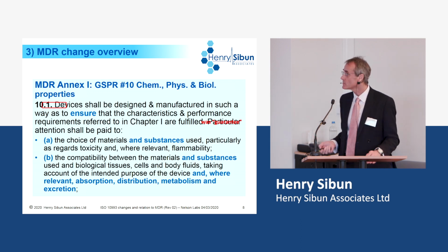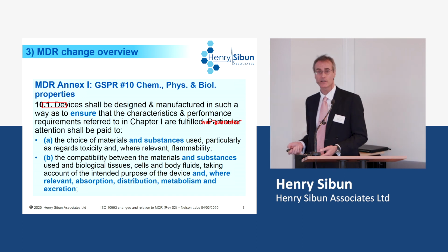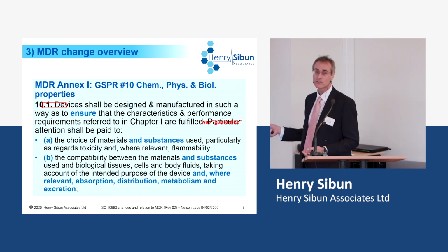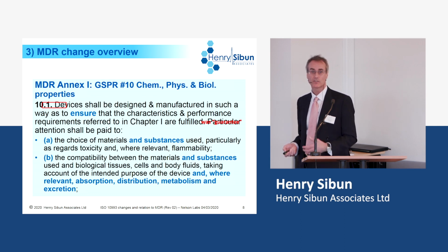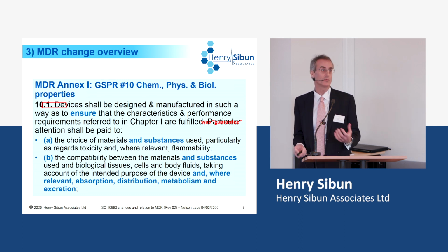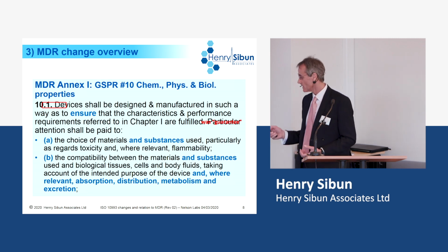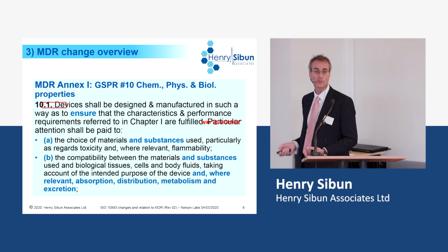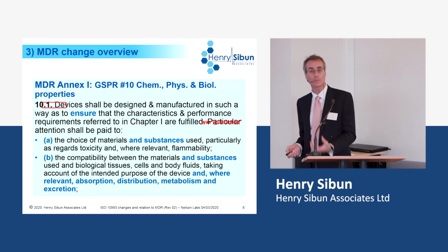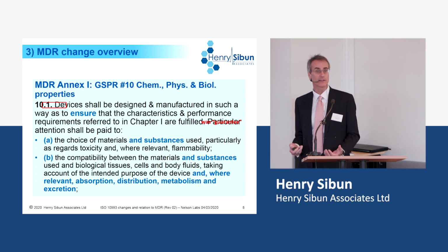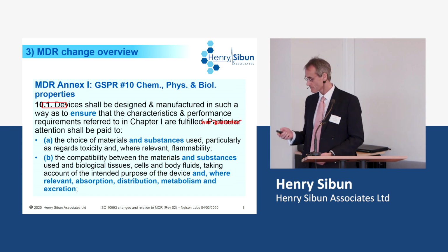And I think in terms of what you'll see from a notified body perspective, then there will be a little bit of a closer look at these. So if you've got devices like an infusion set, you should know what level of, for example, DEHP can leach out of that set to the patient. And maybe you've not looked at that before. And if that chemical is in the patient, how is it metabolized and excreted by the body?